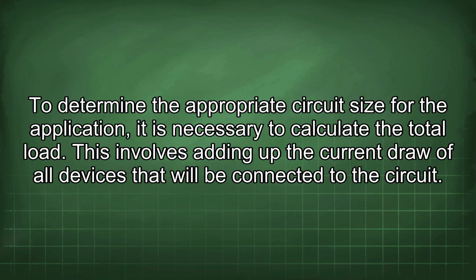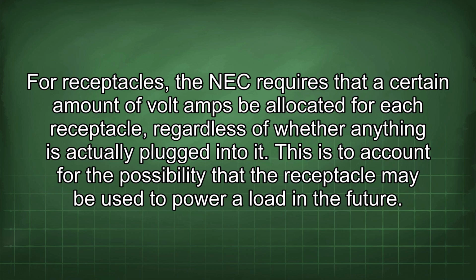To determine the appropriate circuit size for the application, it is necessary to calculate the total load. This involves adding up the current draw of all devices that will be connected to the circuit. For receptacles, the NEC requires that a certain amount of volt amps be allocated for each receptacle, regardless of whether anything is actually plugged into it. This is to account for the possibility that the receptacle may be used to power a load in the future.